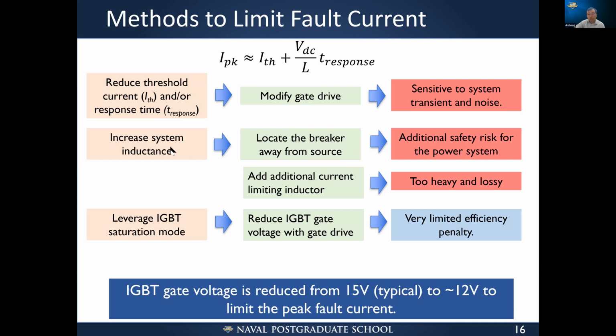We can also try to increase the system inductance and make sure the current will increase slower. We can locate the breakers away from the source to leverage the existing inductance in the system. But this also means additional safety risk for the power system, right? Because with the cables in between, if a fault happens there, the breaker can be bypassed, okay? Or we can add additional current limiting inductors, right?